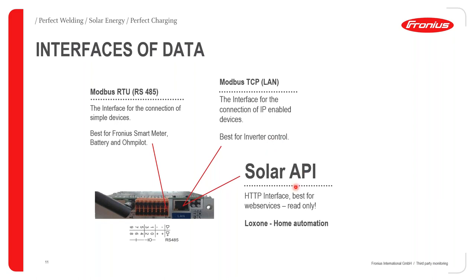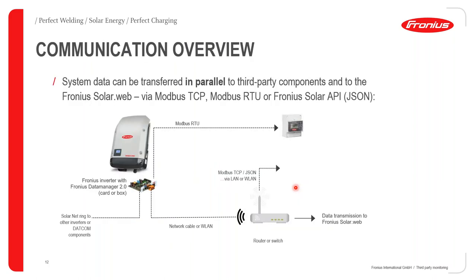As my colleague David Mwangi will cover, the API communication functions via HTTP and is best for web services only — it's a read-only service. System data can be transferred in parallel to third-party components and to Fronius SolarWeb via these communication ports: Modbus TCP, Modbus RTU, or API using the JSON protocol.